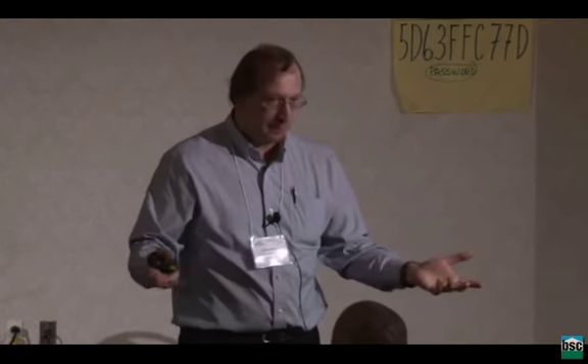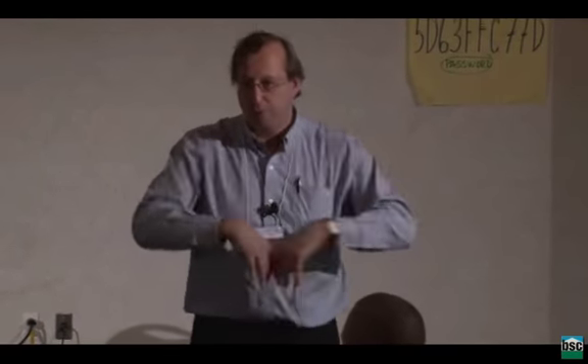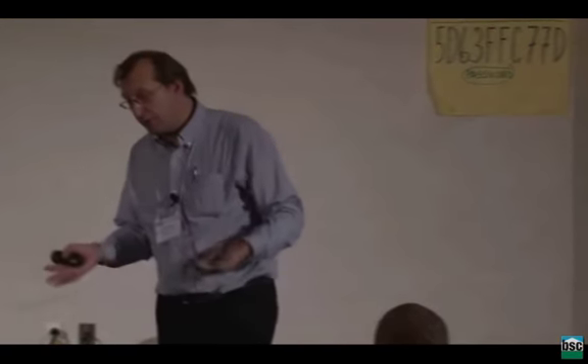Right? If you take a piece of copper pipe and you heat the top, you're going to burn your hand. I mean, it seems obvious, but people are regularly confused by the distinction between fluid like water or air floating up because of the cold falling and thinking that that means I can't heat the ceiling. Baloney. Of course you can heat the ceiling. It's just because that's radiation, not airflow. If we're talking about typical low-load houses, you might end up with 300 to 600 watts of installed electric capacity in a medium-sized room. Typically, you want to worry about cold spots around windows and so on, and offset that with panels that are either above, below, right next to, etc., the window.